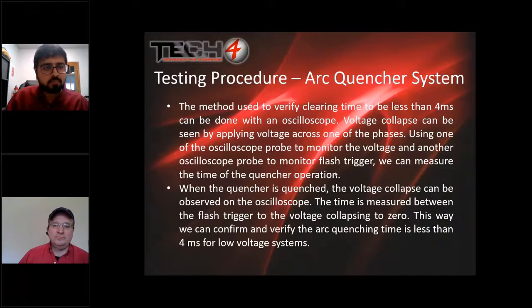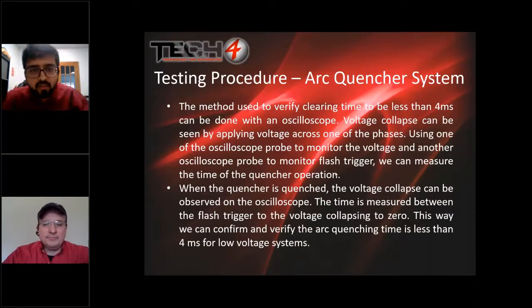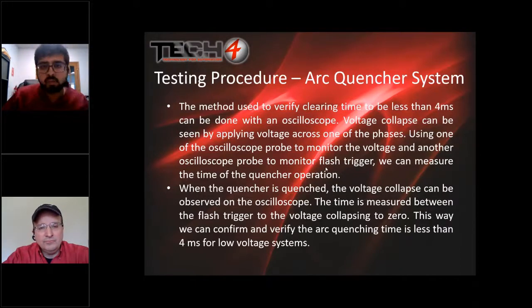So here I explain a little bit more about how we measure the time on the oscilloscope. While testing, while commissioning, while it's in the shop on our floor, we don't have a bus bar to connect to all 3 phases to create a short. So we apply voltage to one of the phases using the same relay test set. We look that up on the oscilloscope. We use a probe so you can see the voltage, and we also use a probe to monitor the flash. When the flash is triggered and the voltage collapses, we can verify the time and make sure it's less than 4 milliseconds. The voltage collapses when the quencher goes off, and we can measure the time between the trigger of the flash and the voltage collapsing and ensure that it is less than 4 milliseconds.